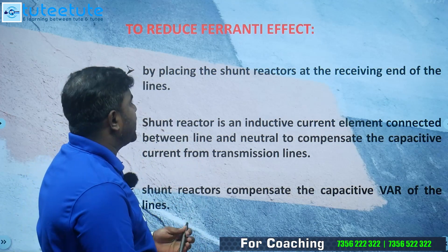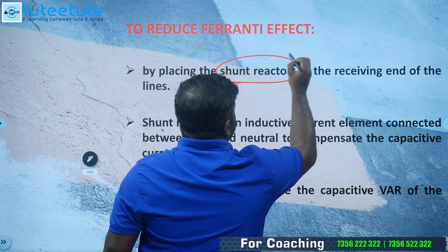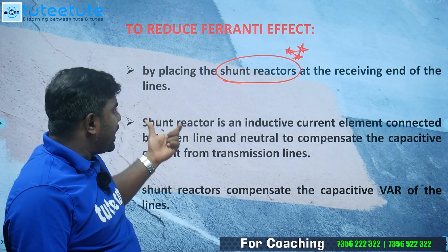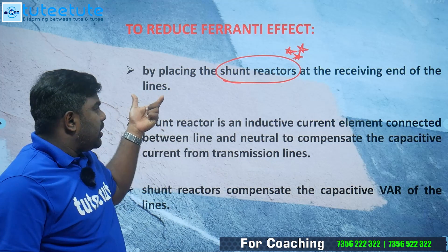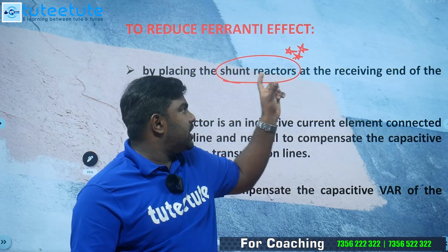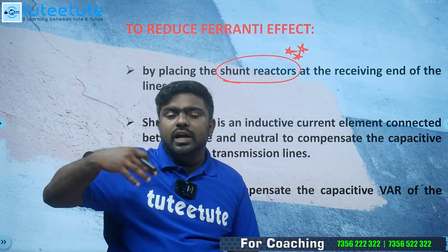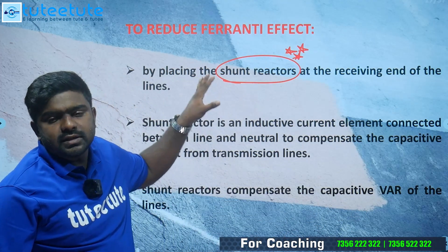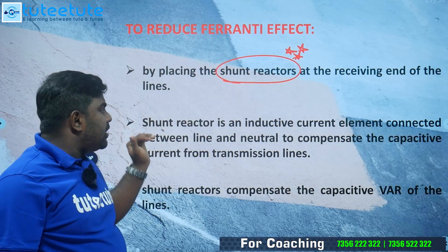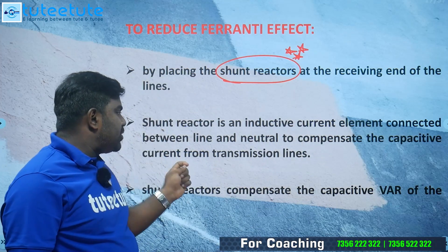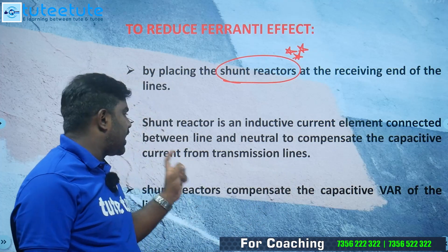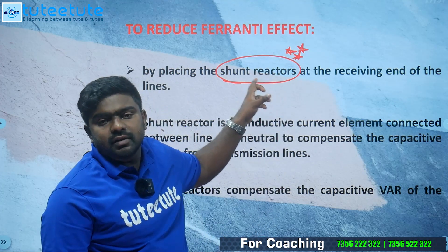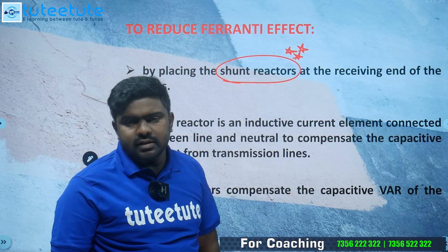By placing a shunt reactor at the receiving end of the line — we call it shunt compensation, shunt reactor — that is a reactive element connected shunt to reduce the receiving end voltage. The shunt reactor is an inductive current element connected between line and neutral to compensate the capacitive current from the transmission line. The extra capacitive current drawn by the line will be compensated by this reactive device, which is the shunt reactor.